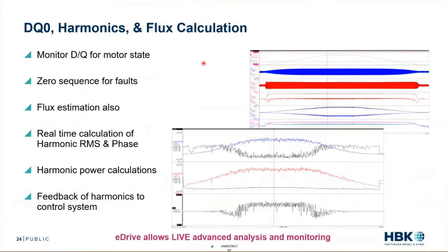We can do a lot of advanced analysis. We can monitor the DQ0 for motor state. We can look at the zero sequence for faults. We can do a flux estimation. We can do real-time calculations of harmonics and harmonic phases. You can understand what the third harmonic of the zero sequence voltage is and view that as a scope trace. We can do harmonic power calculations if you think that an increase in your harmonic power losses will be indicative of failure. And we can feed all of this back to control systems.